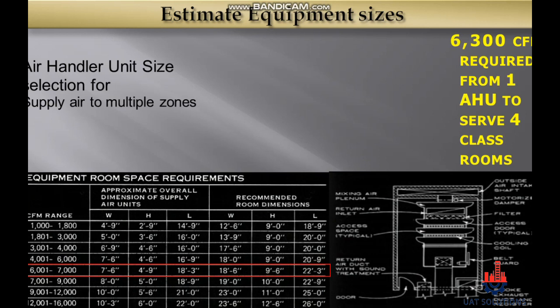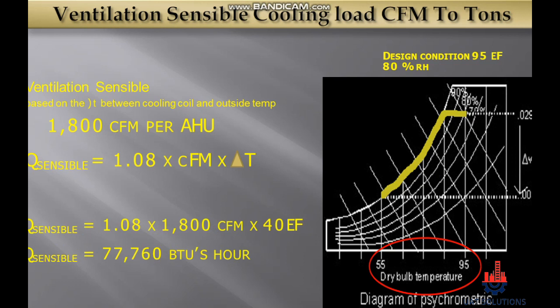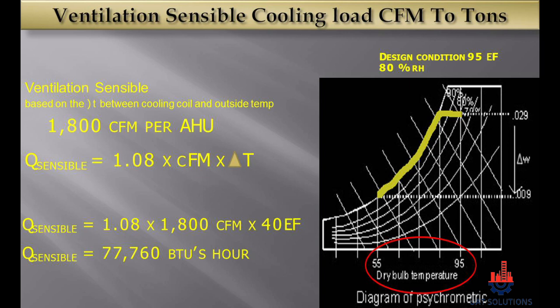The AHU selection table is shown with capacities. To calculate the chiller or refrigeration unit size, we need to perform heat load calculations, which require sensible cooling load and latent cooling load of ventilation, as well as space cooling load. To convert sensible cooling load CFM to tons of refrigeration, we use a ventilation cooling load of 1,800 CFM and a factor value of 1.08. Delta T is room temperature minus desired temperature — 40°F in this example. Multiplying 1.08 by 1,800 by 40 gives 77,760 BTU per hour for sensible ventilation heat.